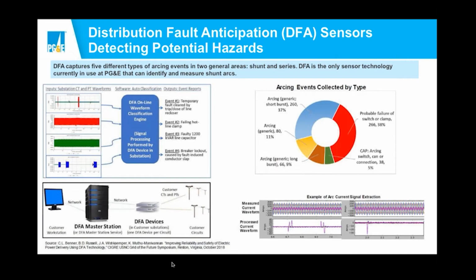Now, one thing to note here: DFA technology, because it's monitoring the entire line, has a hard time telling you where the fault occurred. It can tell you what the fault is, but it's hard to tell where it is. So as you may have guessed, when you start pairing this with technologies like EFD or RF sensors, you can get very effective at finding specific faults on our lines.